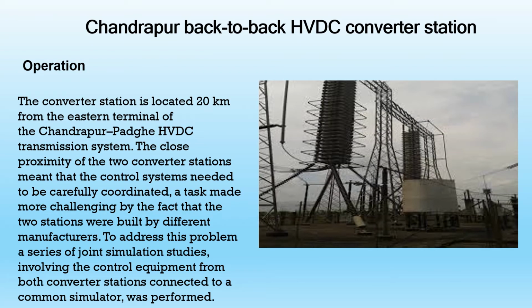Now let's see the operation of Chandrapur back-to-back station. The converter station is located 20 km from the eastern terminal of Chandrapur Padghe HVDC transmission system. The close proximity of the two converter stations means that the control systems needed to be very carefully coordinated, a task made more challenging by the fact that the two stations were built by different manufacturers. To address this problem, a series of joint simulation studies involving the control equipment from both converter stations connected to a common simulator was performed.